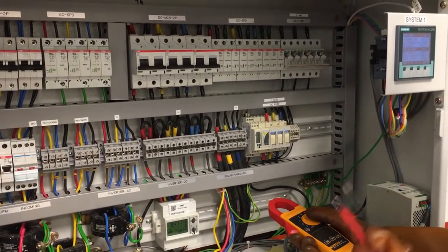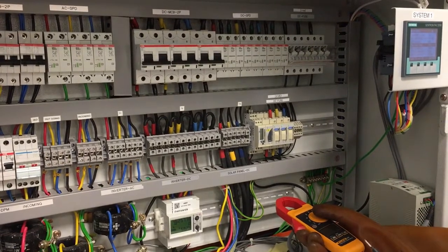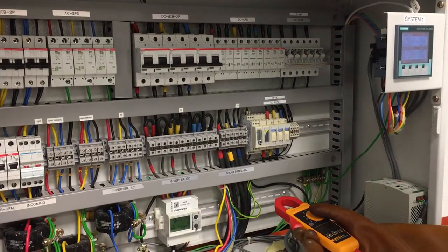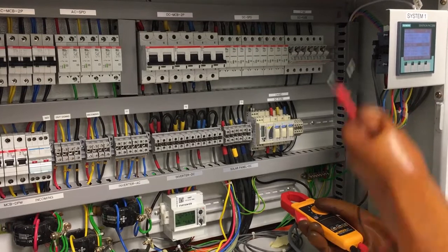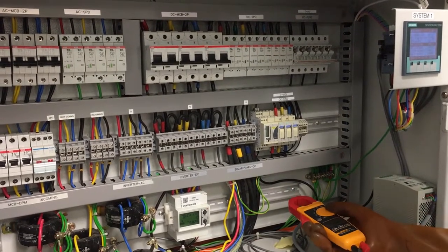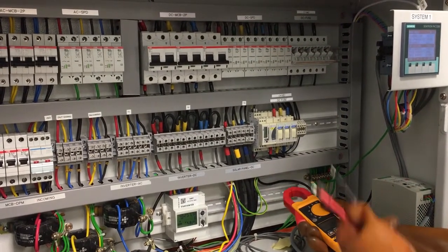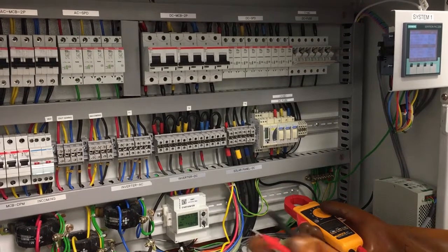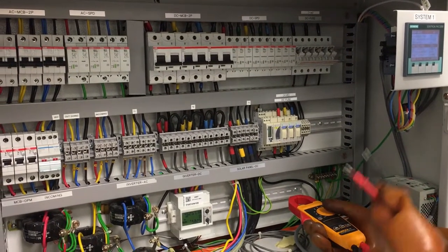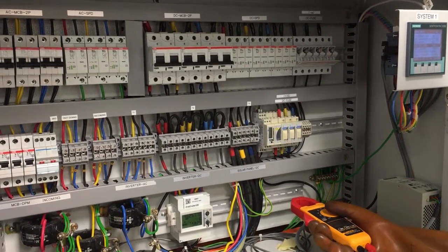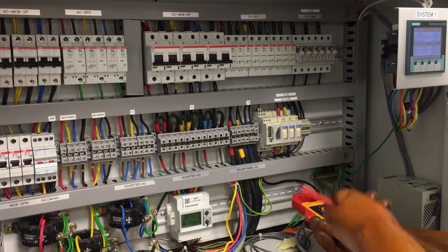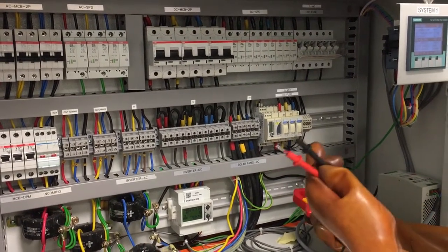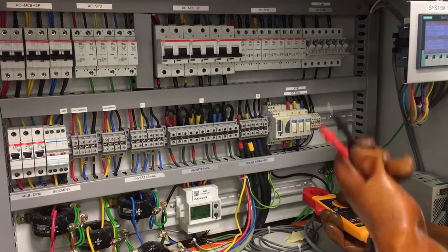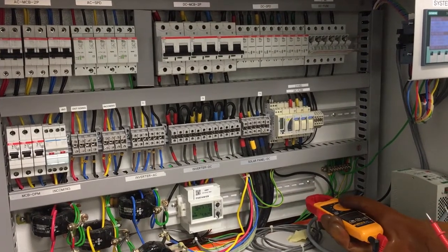the voltage does not exceed the maximum inverter voltage. Now from the data sheet, I already know that the inverter has a maximum voltage of 700 volts. So this one is 267, so well below the maximum, so it's going to be safe for us to turn on. If when we measure the value is larger than 700 volts, then we should not turn it on because it can damage the inverter.